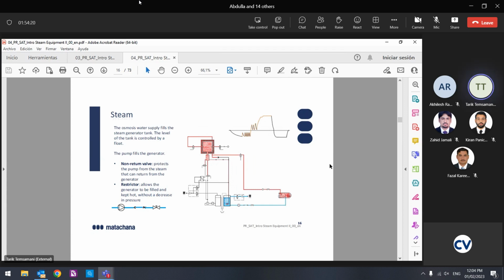The one-way valve is there because the pressure in the steam generator is higher than the pump pressure. The hot water cannot return to our pump and damage it. This pressure cannot reach the pump. Inside we always have 3 heaters and a water level. In the case of the SC500, there are 3 independent floaters, and in the case of the 1000, there is 1 triple floater.